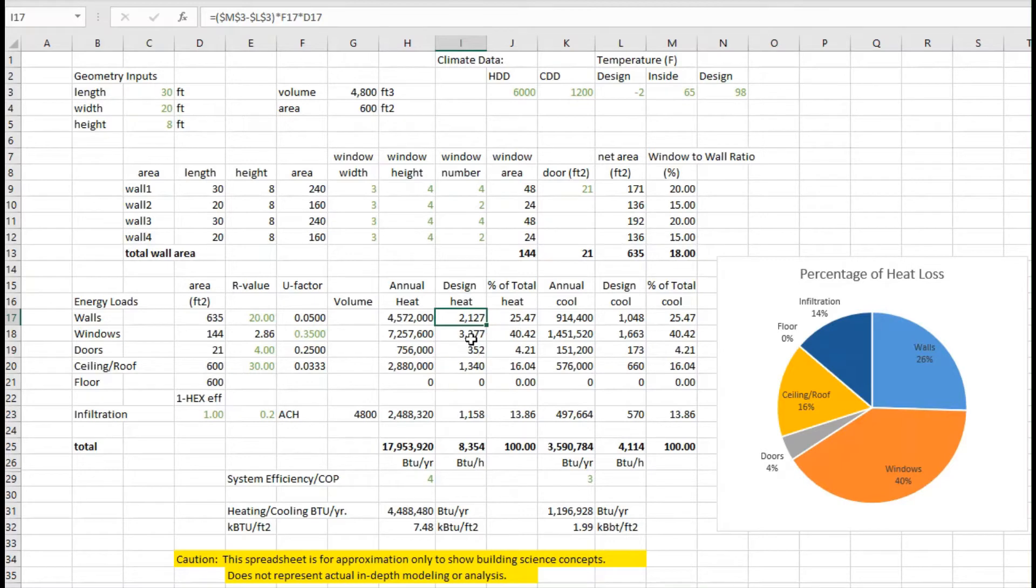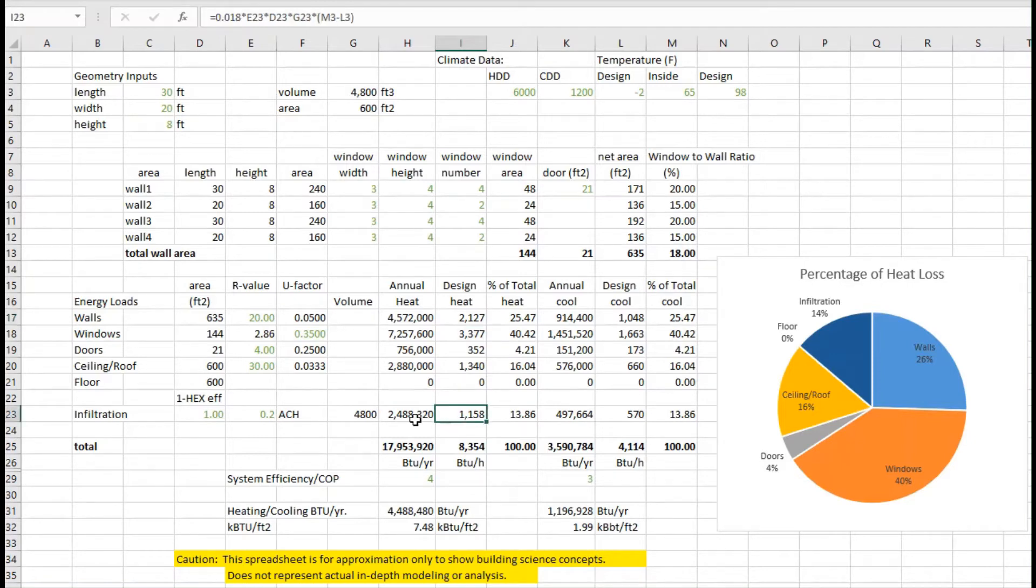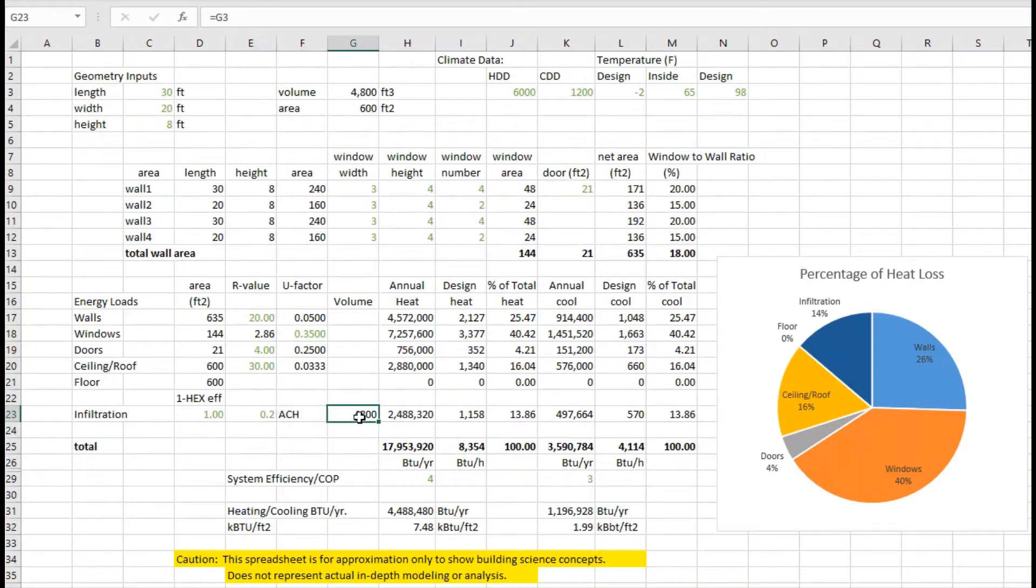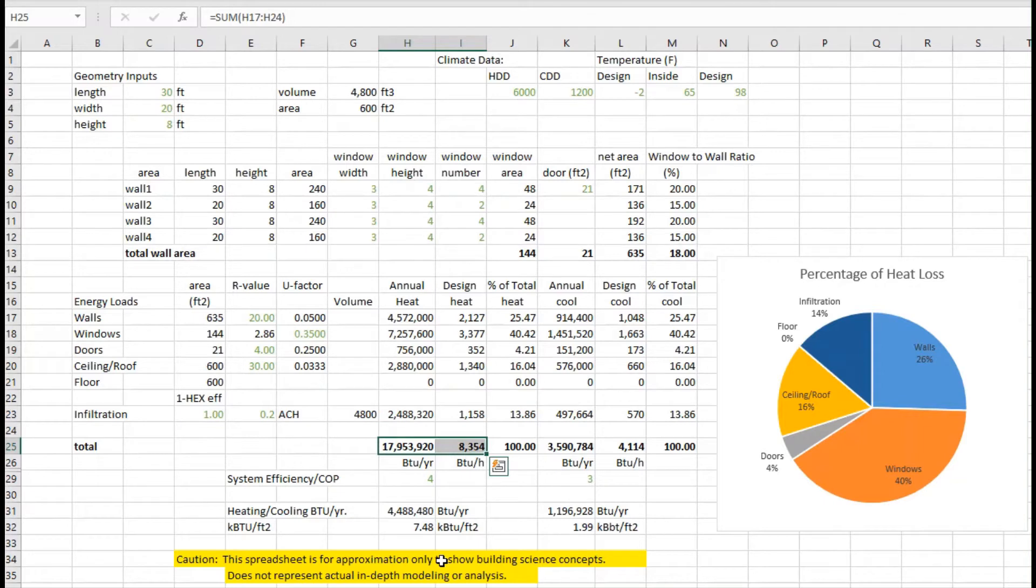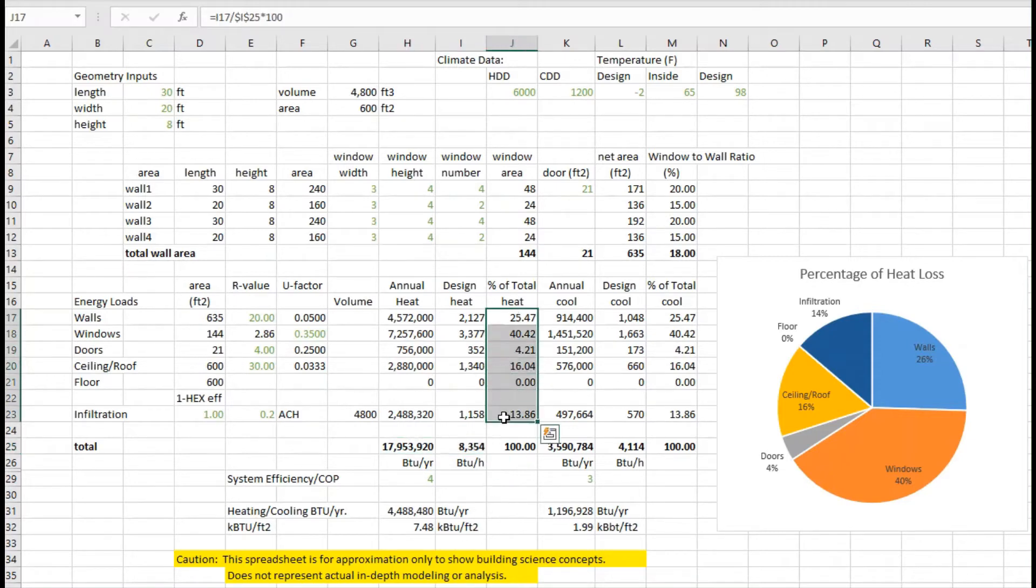Looking through all of these, I can then also calculate the infiltration, so taking an air exchange rate of 0.2 air changes per hour. I had the volume from before, and calculate again both the annual heat and the design heat loads. And from that I can come up with a total number, compute what the percentage is through each of those surfaces, and the contribution infiltration.